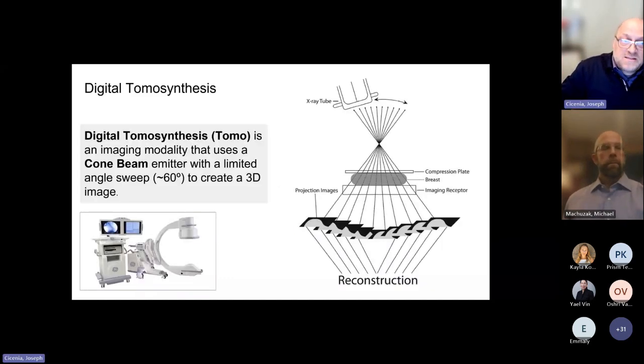Digital tomosynthesis, or digital tomo, is an imaging modality that also uses a cone beam emitter - pretty much what's on everybody's fluoroscope machine. Same emitter, same physics, same everything. The only difference between a cone beam CT and digital tomo is that this cone beam emitter has a limited angle sweep, 60 or 90 degrees, and that's what differentiates it from cone beam CT.